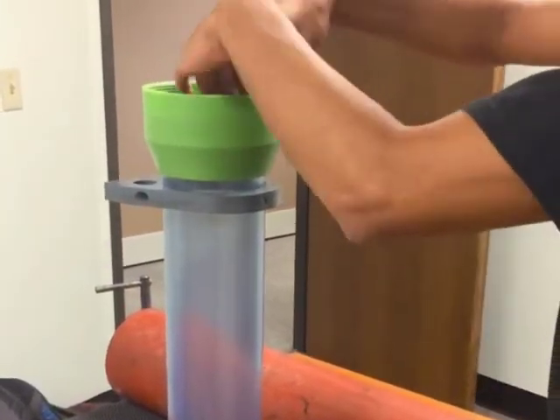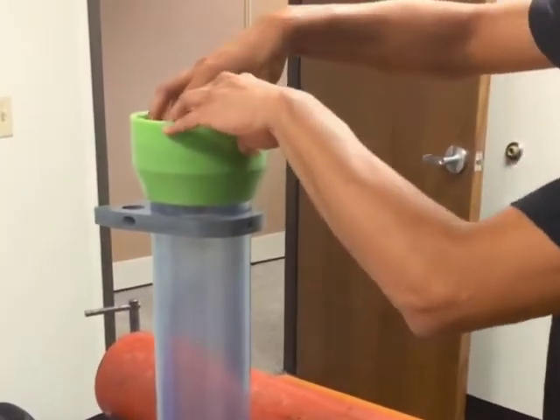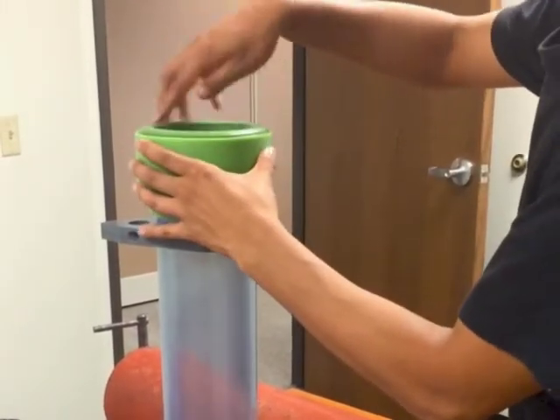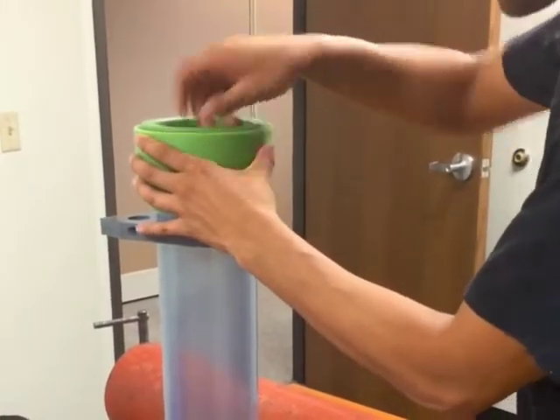The system's offset calibration is done prior to every measurement. The cal ring, a four inch cal ring in this case, is inserted and secured into the calibration tube.